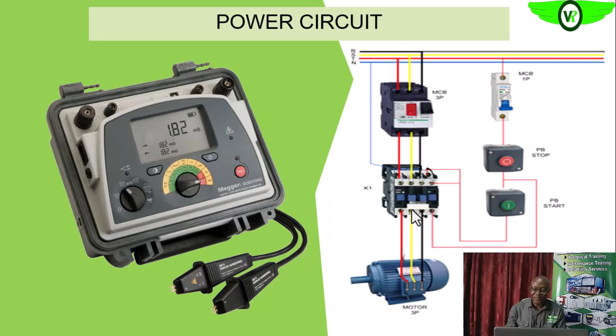what you'll be doing, if assuming we have a star connection, that is, you are testing the resistance of this conductor, okay, through one winding in the stator coil, okay, and then through another winding, that is the second phase winding, then this yellow conductor to this point. Are we getting it?